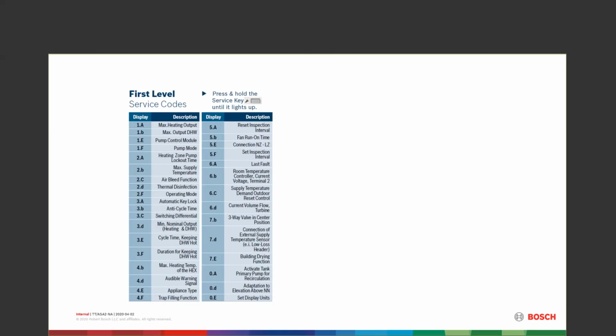Current volume flow for your turbine is under 6.D. Absolutely use that all the time in troubleshooting for domestic hot water, so you'll be able to see what you're actually doing. And then the other one that we use fairly often is 0.D, as in David. That's going to be your elevation adaptive setting.